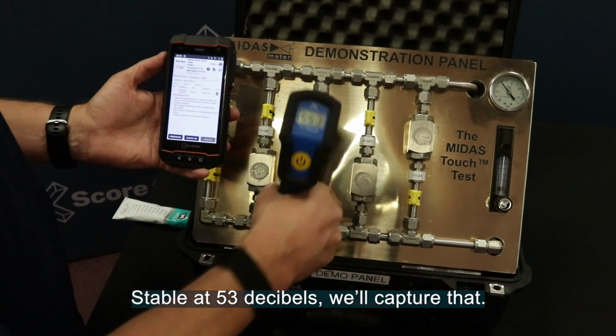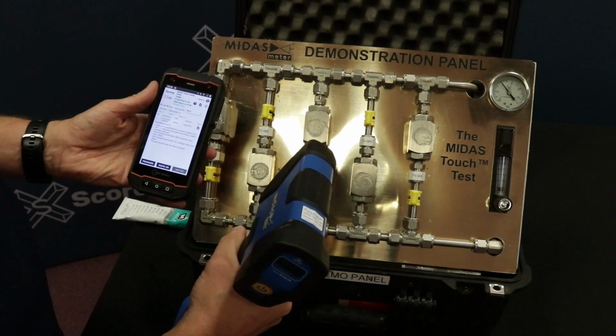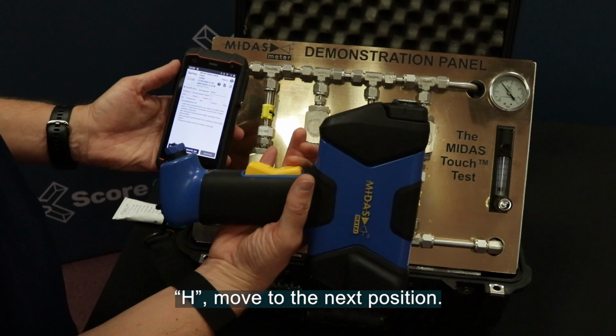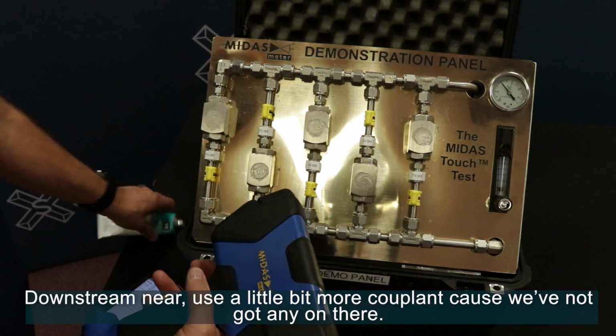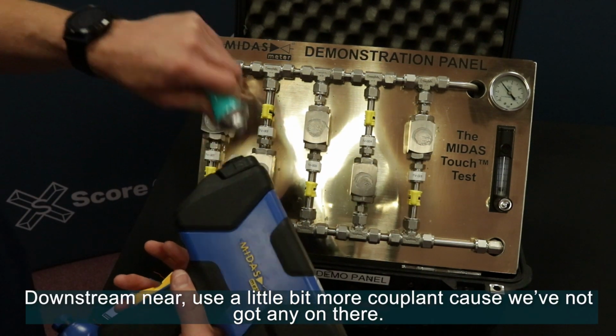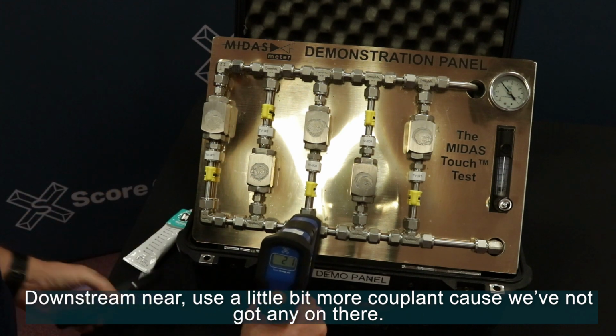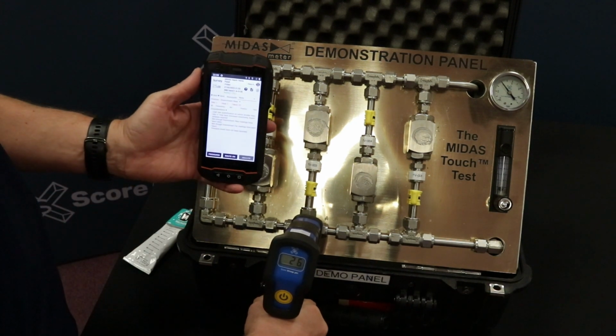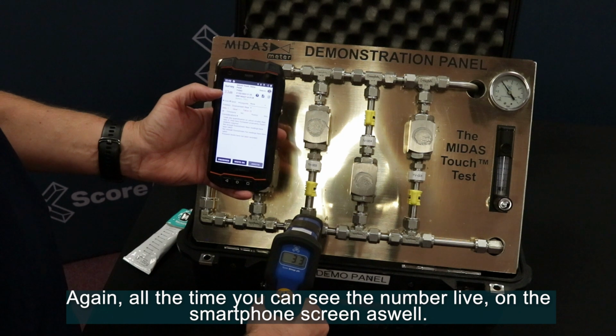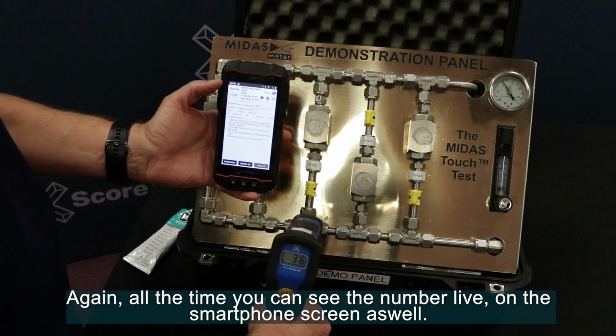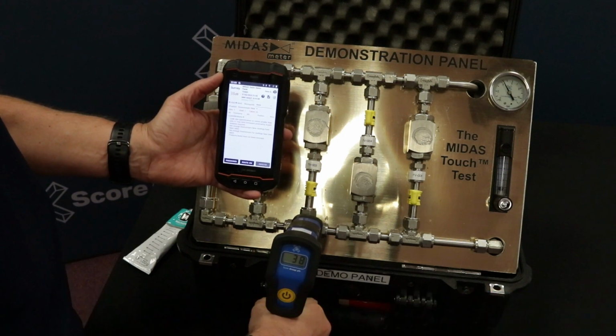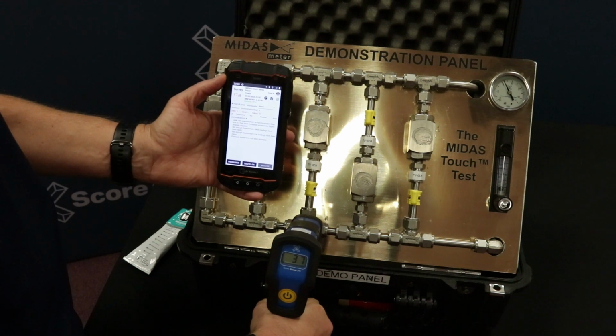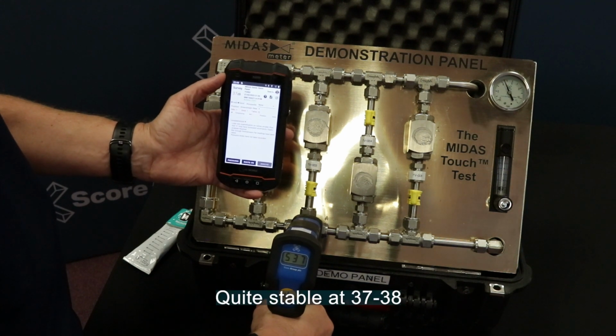Stable at 53 decibels, we'll capture that. H, move to the next position. Downstream near, use a little bit more couplant because we've not got any on there. Again, all the time you can see the number live on the smartphone screen as well. Quite stable at 37, 38.